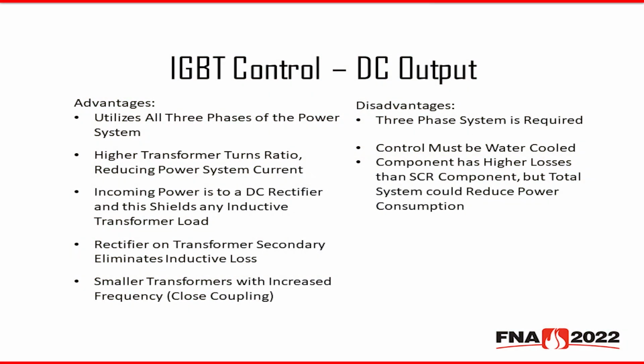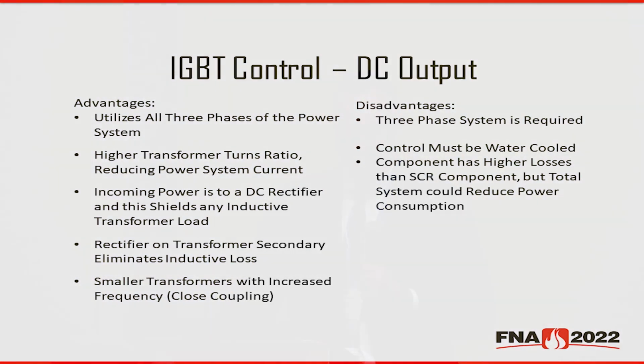A summary of the advantages can be seen here for an IGBT MFDC control. Some of them include it utilizes all three phases of power and balances the three phases. The higher transformer turns ratio from that higher voltage allows a lower peak current demand through the system. Another point is that if you have any inductive loads, that DC completely eliminates the inductance in that load, whereas with typical SCR, VRT, any type of control type, you're not removing that inefficiency, you're just masking it with either capacitance banks or power correction in your facility. With an IGBT MFDC system, that inefficiency is just not there in the first place. Again, the smaller transformers with the increased frequency allow the infrastructure to be smaller and to move those power supplies closer to your power feed-throughs.